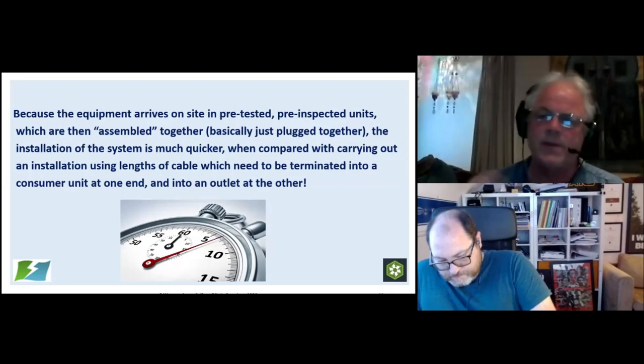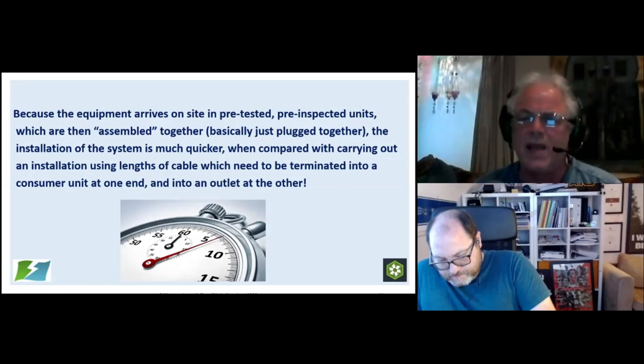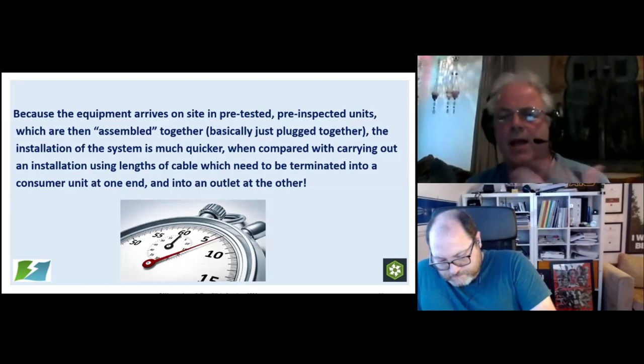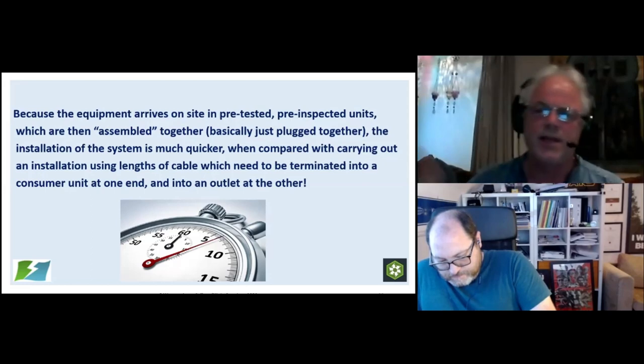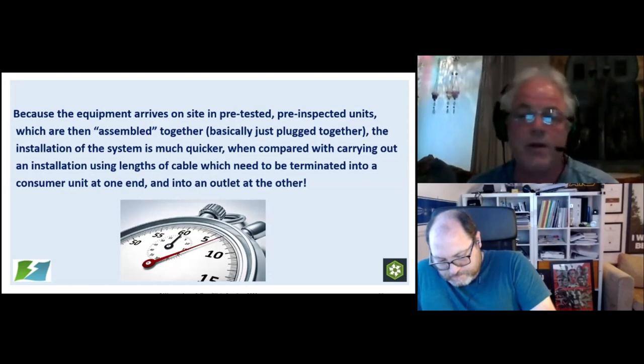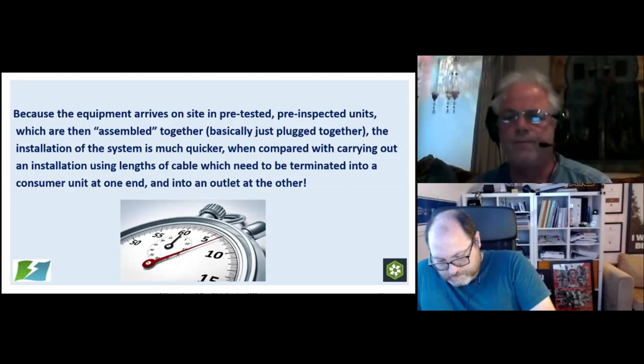As to the design, design is still important, and this is one of the issues we have with temporary systems: any fool can put them together. If we put a load of temporary equipment into a schoolyard, so a load of distro, a load of leads, and loads of other bits and pieces, the kids would soon see what fitted where, and they'd be able to put a system together. Now, would it be safe? Probably not. Would it be usable? Probably not. Okay. So it needs, obviously, to be installed as per design, but the ease of use and the ease of installation and putting it together must not be overshadowed by safety and so forth.